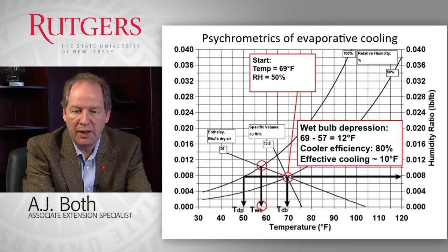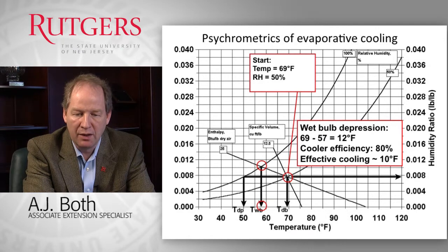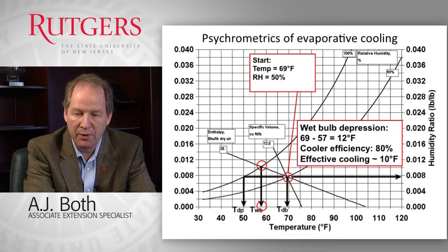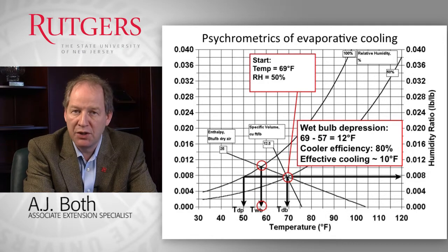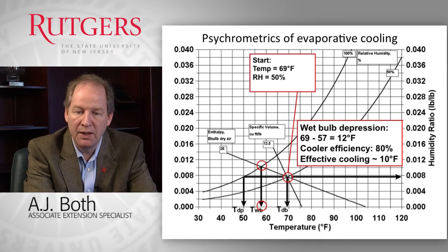One tool we use to evaluate how evaporative cooling systems work is the psychrometric chart. On the horizontal axis we look at temperature, and on the vertical axis we look at humidity ratio, which tells us how much water vapor is present in a quantity of dry air. In greenhouse environments we typically work with temperatures and relative humidities to characterize conditions, and the psychrometric chart allows us, by knowing two conditions such as relative humidity and temperature, to quickly identify the other conditions important for understanding what changes are occurring or can occur in an evaporative cooling system.